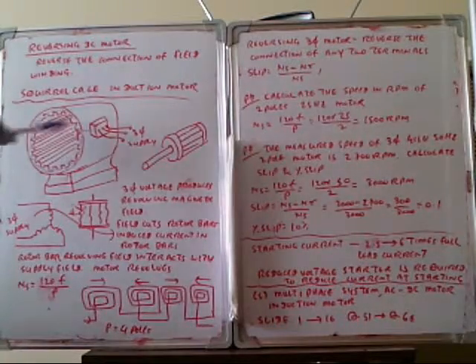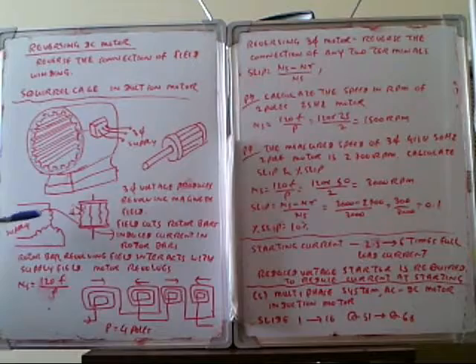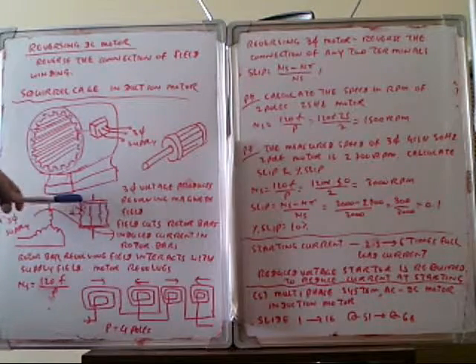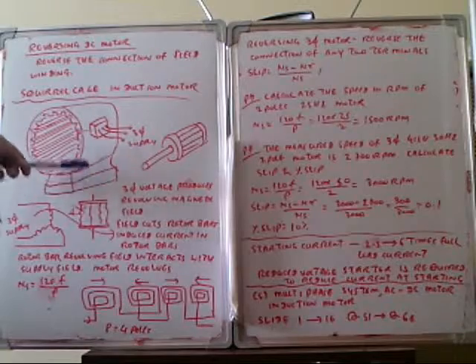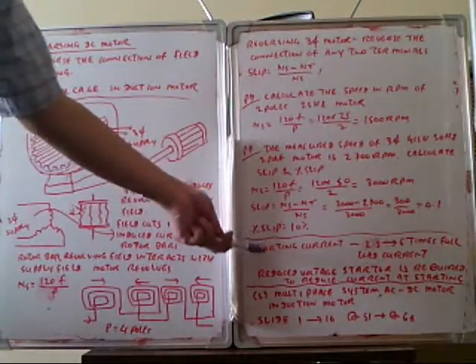So on the three-phase squirrel cage motor, the rotor bars are connected to the cage, similar to a resistor connected in series. When you connect the resistance, the resistance is low and the current is high. Therefore, for the three-phase squirrel cage motor, the starting current is about 5 to 6 times full load current.